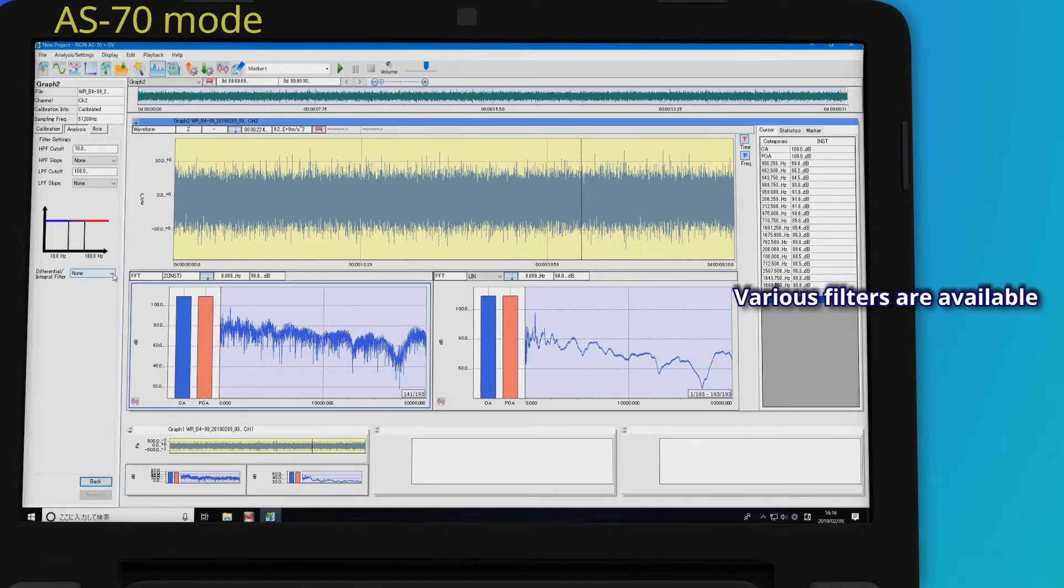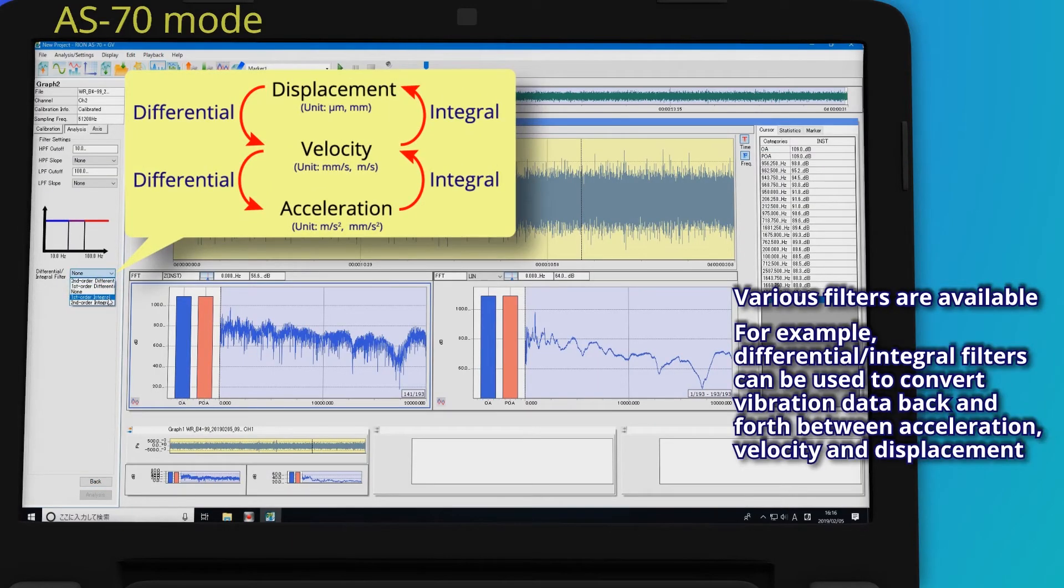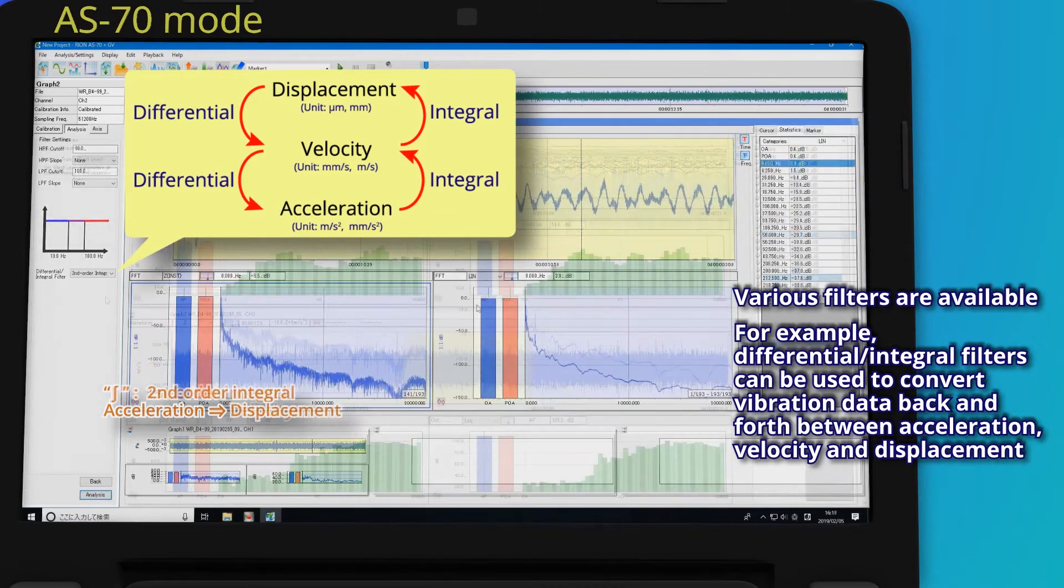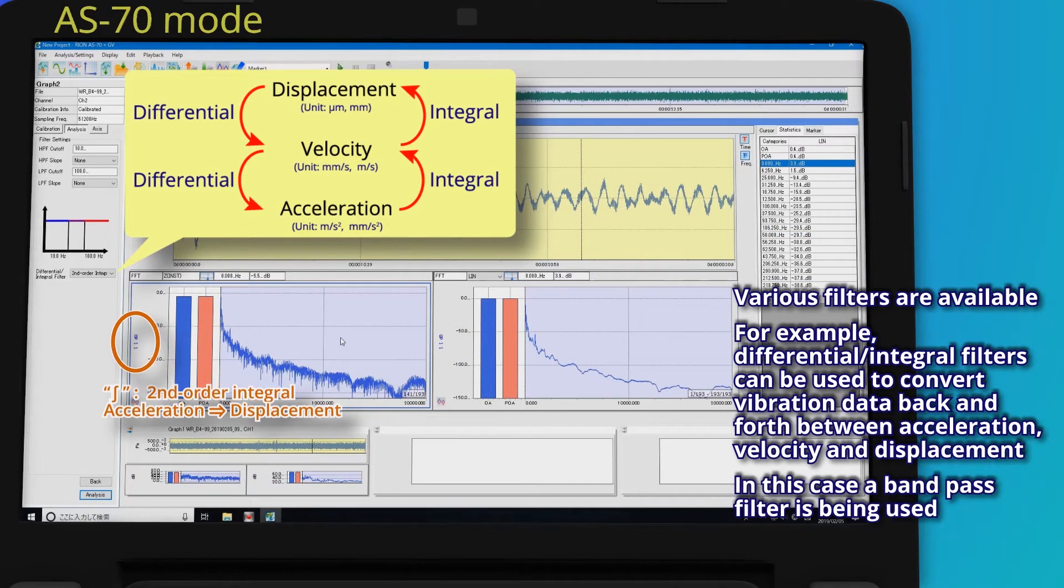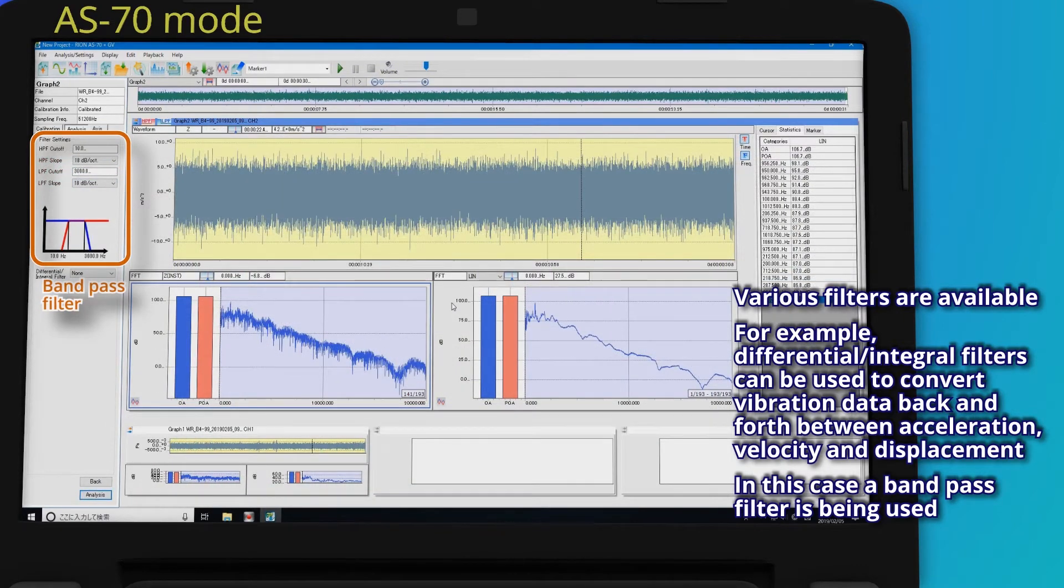Various filters are available. For example, differential integral filters can be used to convert vibration data back and forth between acceleration, velocity, and displacement. In this case, a band pass filter is being used.